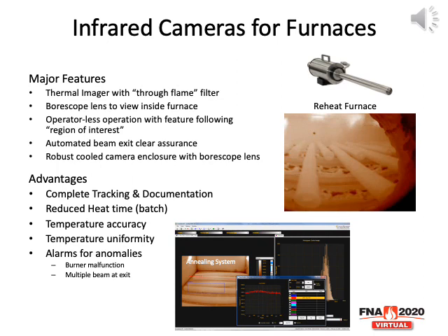Another important feature is the borescope optics. These are the long optics that allow the camera to get a small hole into the furnace and give a wide view internally, but the electronics from the camera are safely on the exterior of the furnace, and this is what enables continuous operation with low maintenance for many years.